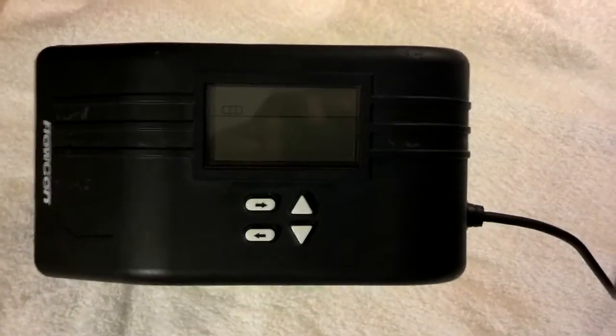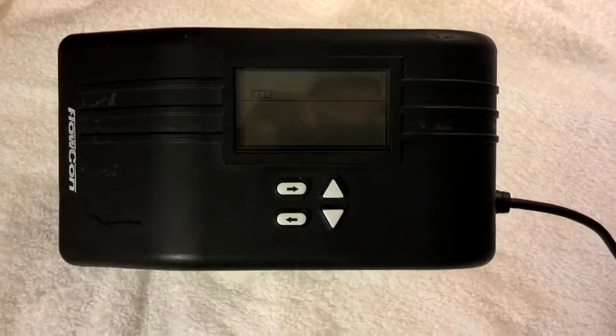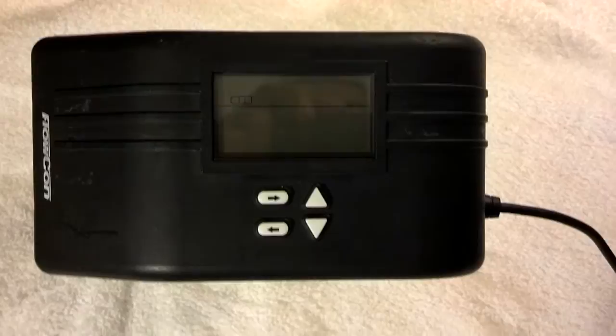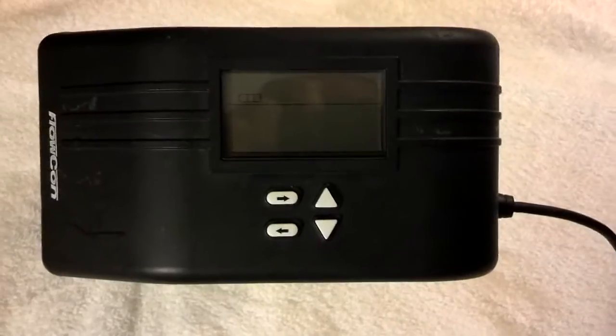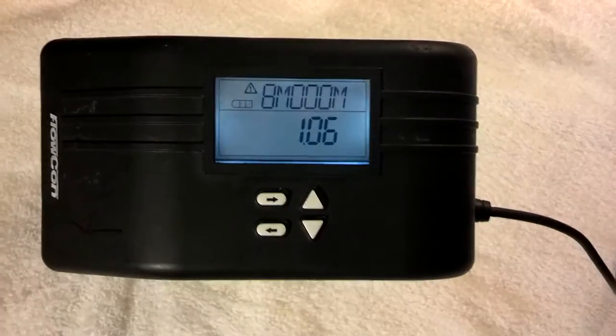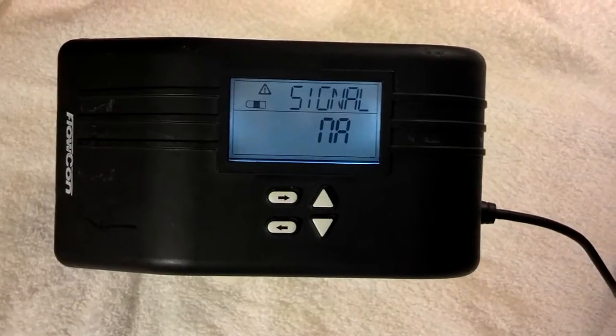This video is going to show how easy it is to program the Flowcon SM digital actuator. Right now the unit doesn't have any power on it and I'm getting ready to put 24 volts to it. As soon as you put 24 volts to it, the screen is going to light up and it's going to go into a calibration mode. The actuator is actually going to stroke the valve closed and it's going to be able to program itself to find out where the top and bottom stroke values are.